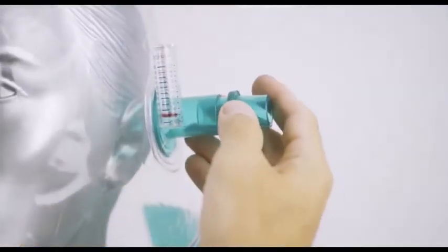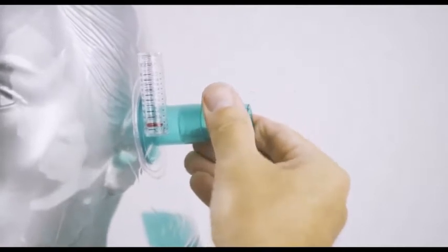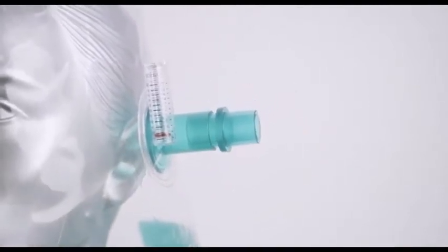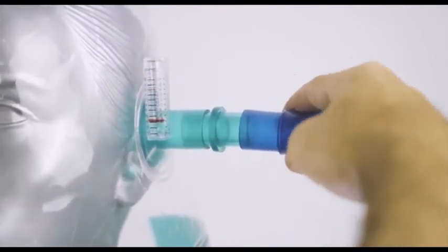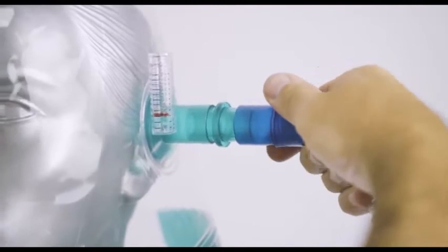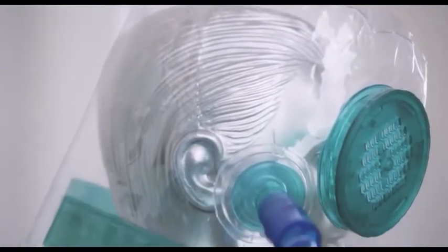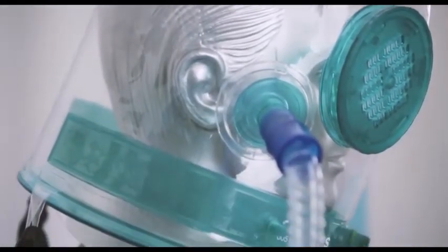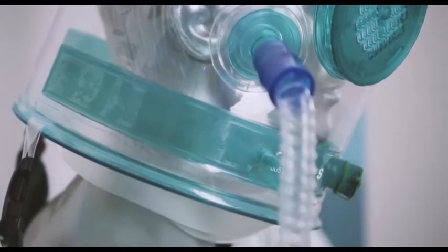With the helmet, a male-to-male adapter is provided to connect the outlet with an external ventilator, for use in a dual-tube CPAP therapy. Regardless, by international guidelines, it is preferred to execute the CPAP therapy with a high-flow generator and a PEP valve, instead of a ventilator. A pocket on the inlet connection directs the flow tangentially to the inner surface, to reduce noise inside the helmet and to avoid air against the patient.